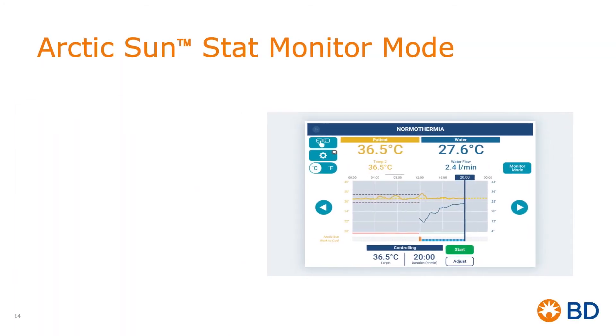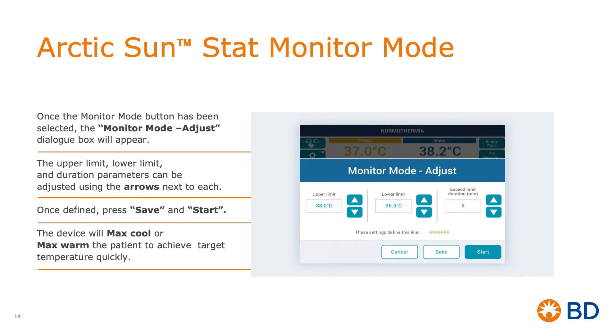Once the monitor mode button has been selected, the monitor mode adjust dialog box will appear. The upper limit, lower limit, and duration parameters can be adjusted using the arrows next to each. Once defined, press save and start.